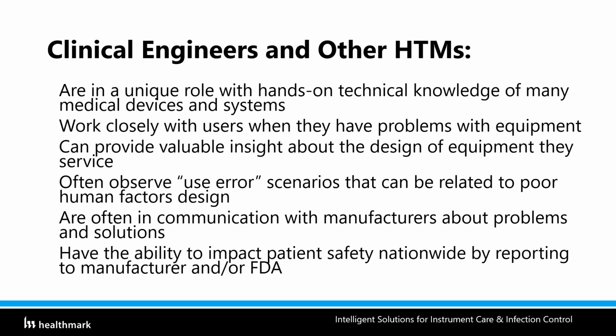If a device is working perfectly, obviously, we don't get a call, but if a device is new and there are a lot of use issues, human factor issues, we get a lot of calls, and we document those. I know some maintenance management systems let you code those to know how many user issues you receive, and how many of those issues are related to the use of the technology. We point out obviously a design issue versus just a user not knowing how to use it, and we are often in communication. So hopefully you feed that information back to the manufacturer. As a biomed, we used to contact device manufacturers, constantly going back and forth if you had an issue. So hopefully you get that as feedback.